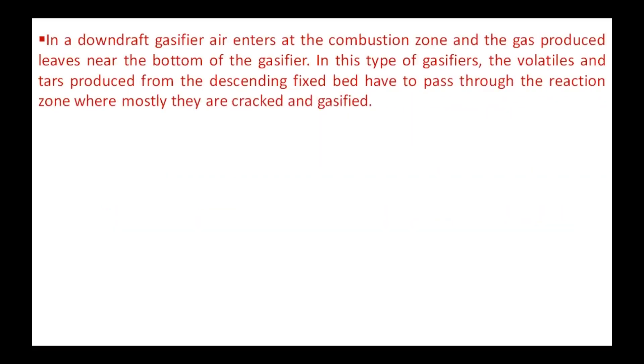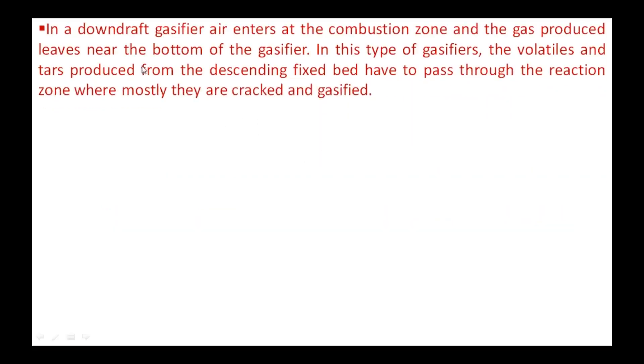In a downdraft gasifier, air enters at the combustion zone and the producer gas leaves near the bottom of the gasifier. In this type of gasifier, the volatiles and tars produced from the descending fixed bed have to pass through the reaction zone, which is a constriction at the highest temperature, where they are mostly cracked and gasified to form gas.